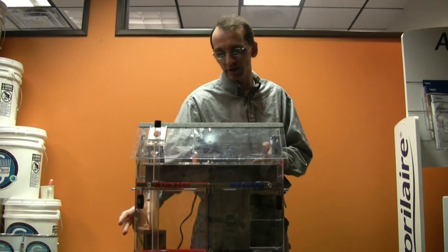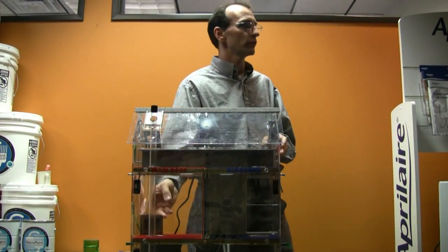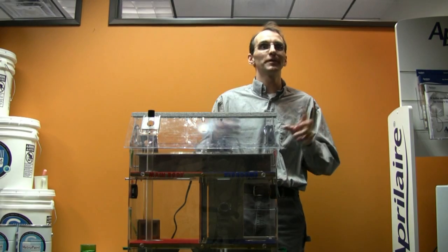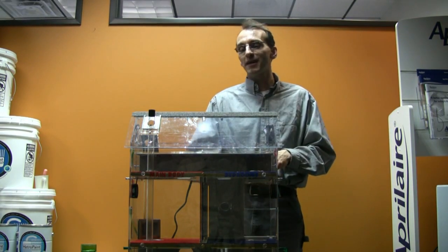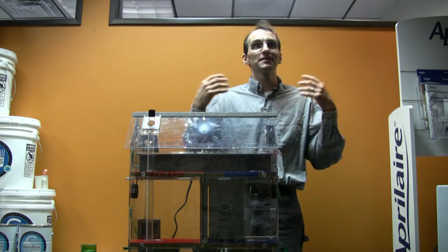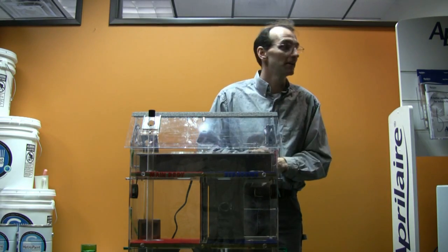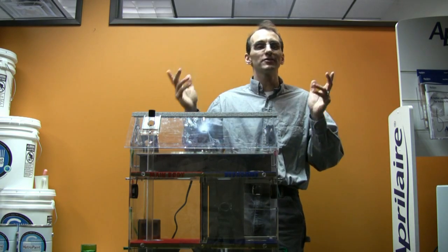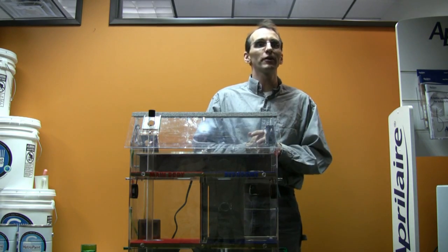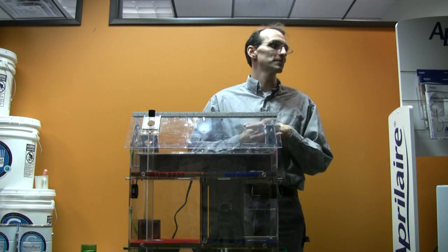Other ones that we don't think about as much that can be issues are really your fireplaces in the home. We don't think about our living room as a combustion zone, but when you have a fireplace in there, it is a combustion zone. And oftentimes that's right near the kitchen and you just did the fancy kitchen remodel and somebody talked you into putting a 600 CFM range hood in the kitchen, and so that happens to be the day that you're running it because you have people for dinner and you have a fire going and you can't seem to get the flue going very well and you keep backdrafting smoke into the house.